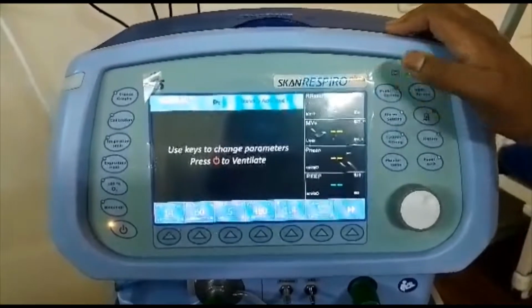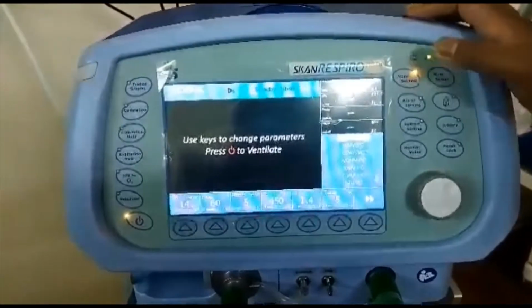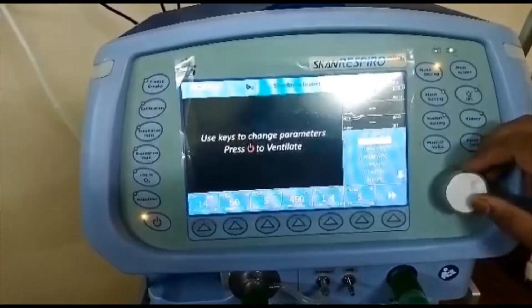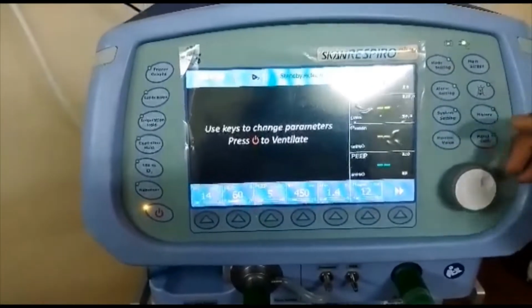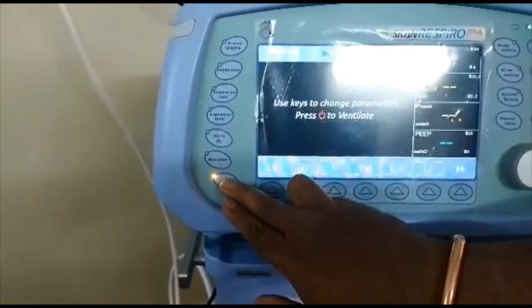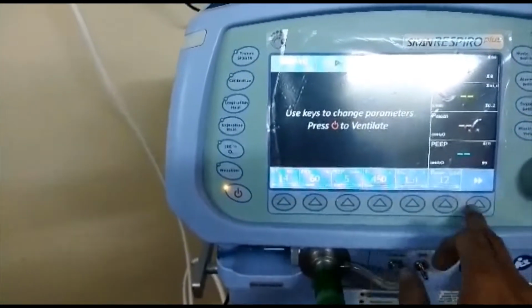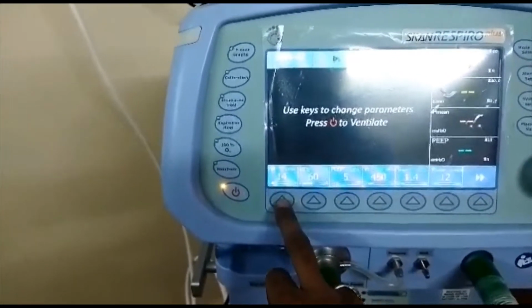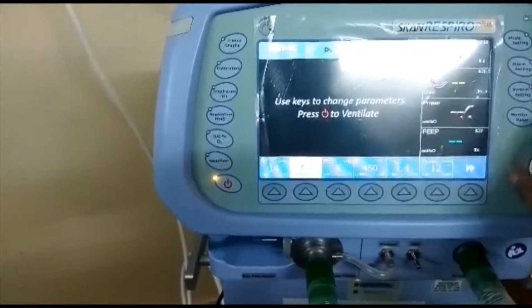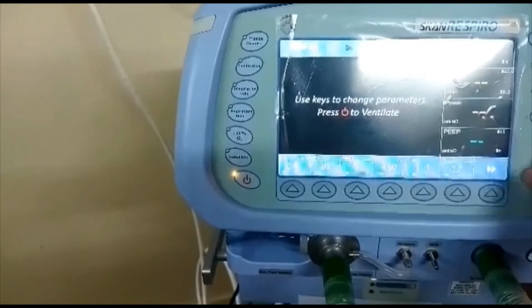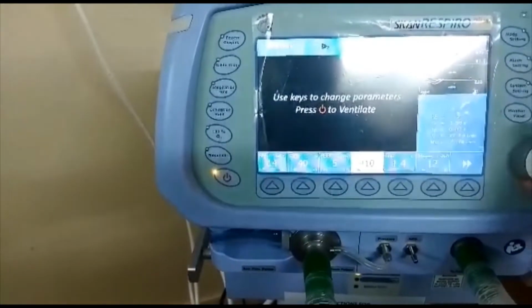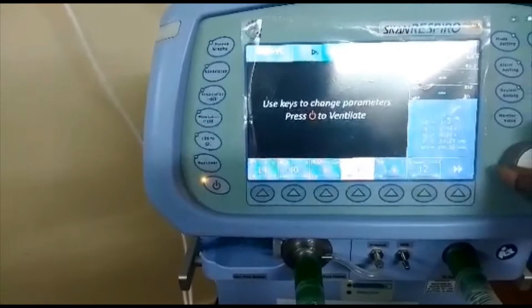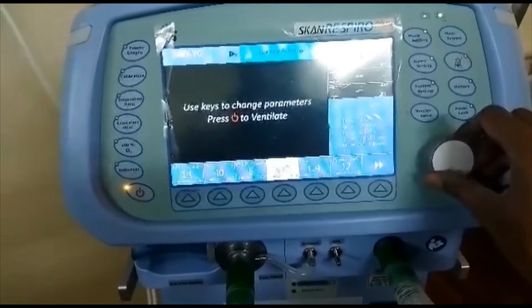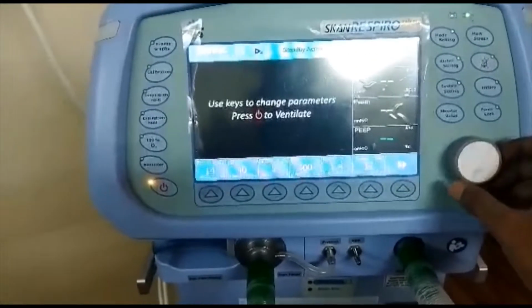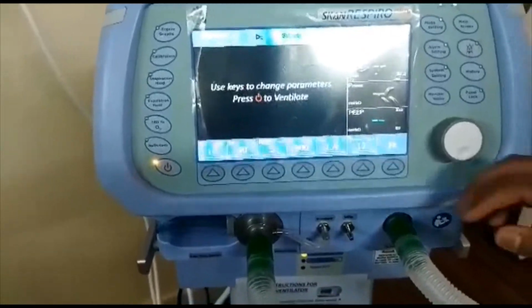To start up the ventilator, we have to go to mode settings. So in mode settings, SIMV mode. The parameters we can set here. So respiratory rate and FiO2 can be adjusted. Tidal volume can be varied. So I kept 400. Now start ventilating.